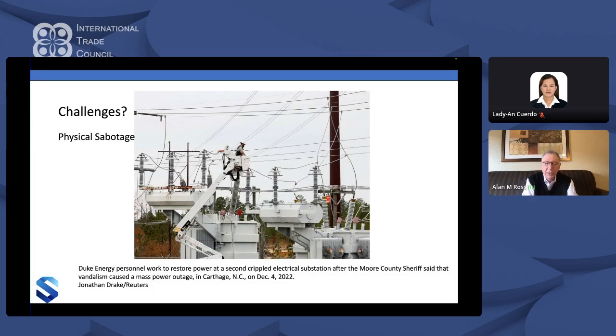Physical sabotage. Two or three weeks ago I was in Sacramento moderating a panel with the Sacramento Municipal Utility, PG&E, and Idaho Power. They were selected for a reason. The three experts who came shared the amount of physical sabotage they've had—people wantonly trying to destroy electrical equipment, shooting at transformers, trying to put holes in the transformer radiators so the oil drains out and the transformer overheats, shuts down, and creates a problem, or shooting at bushings. If you hit a bushing, many times you can create an explosion and an oil spew and a fire that can't be put out by fire crews—it has to burn out. And if you get a 5,000 gallon oil-filled transformer, it can take days to burn out, so you can't even go in and do remediation or resilience planning.